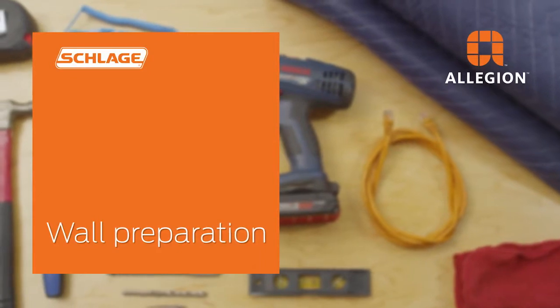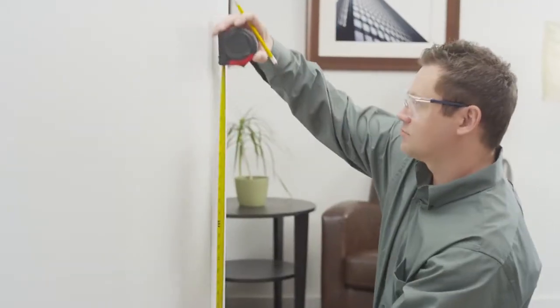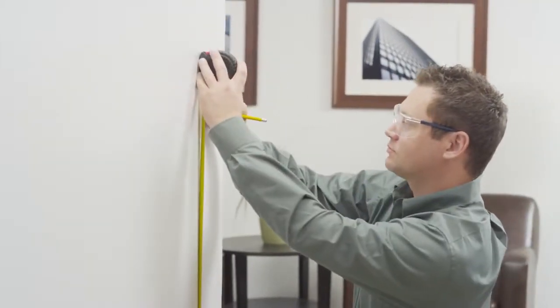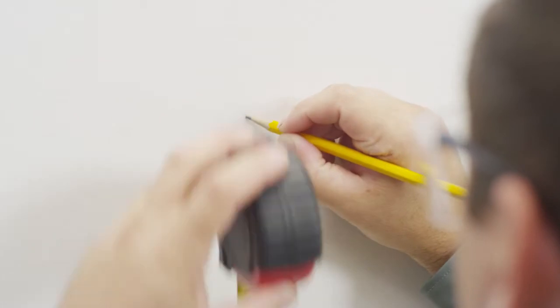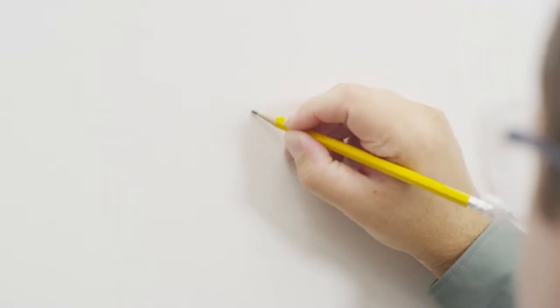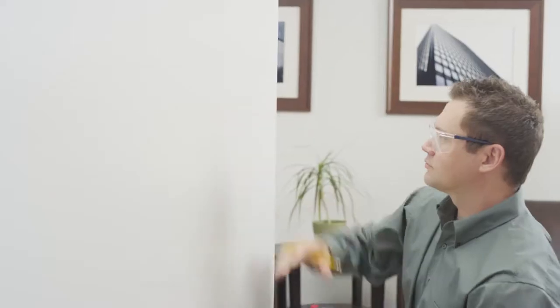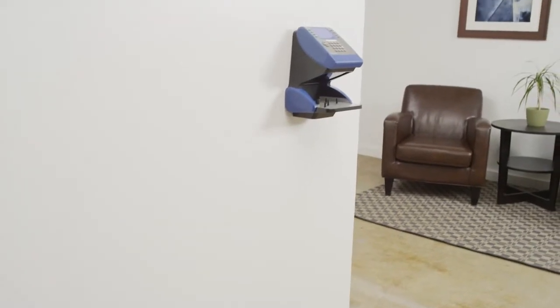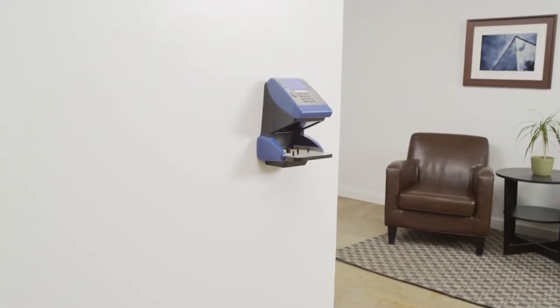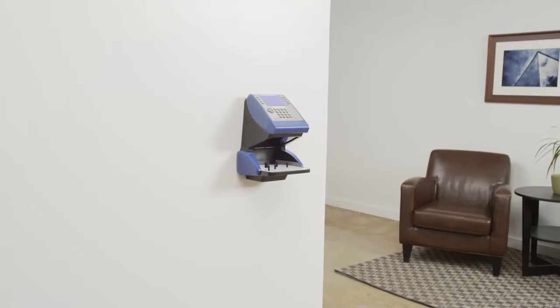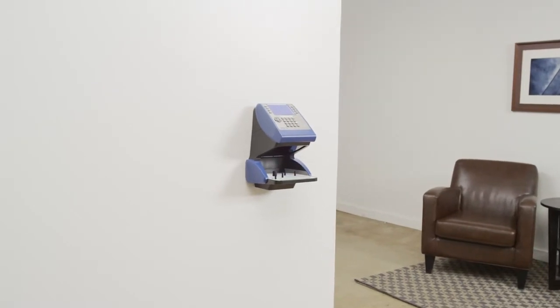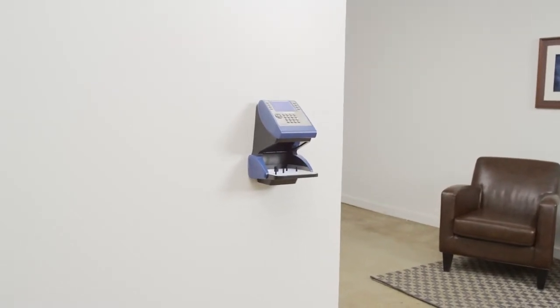Before proceeding, please take appropriate safety precautions. Measure and mark a point 49 inches or 125 centimeters from the surface of the finished floor. This point is used by the leveling hole where the top center point of the terminal should be mounted. At this height, the unit's platen will be 40 inches or 102 centimeters from the floor. This conforms to the Americans with Disabilities Act standards.